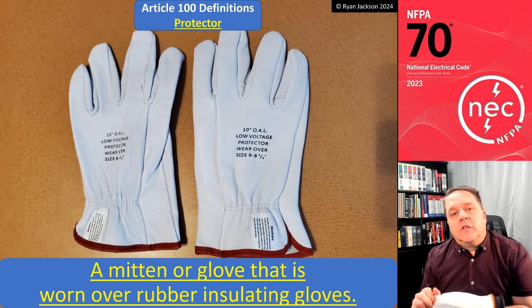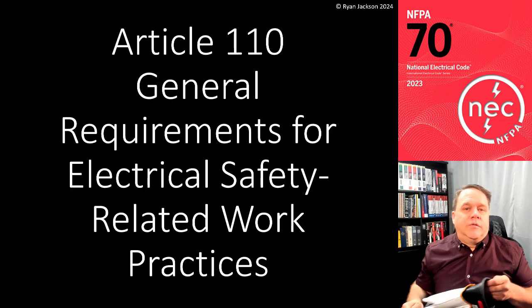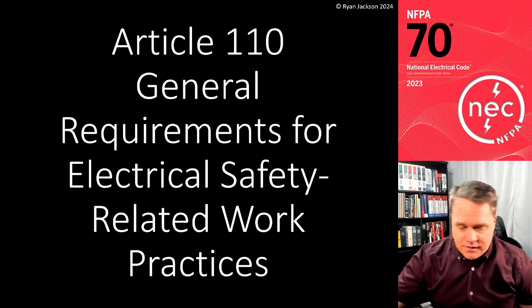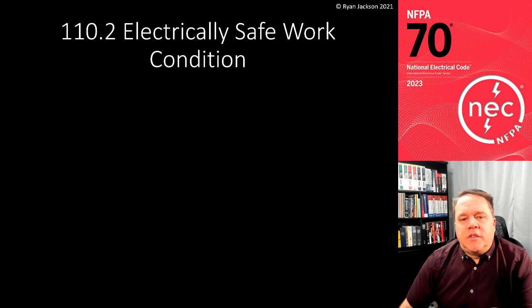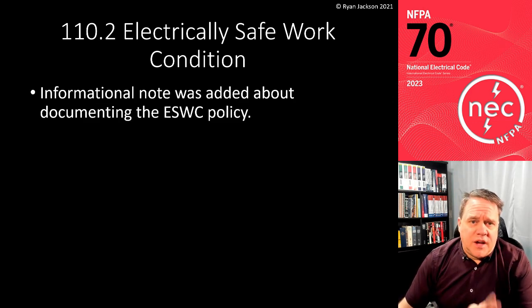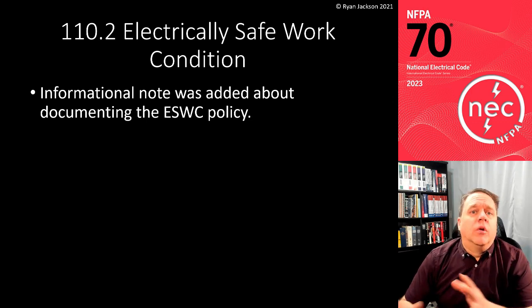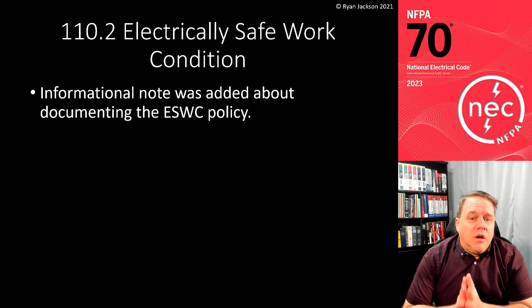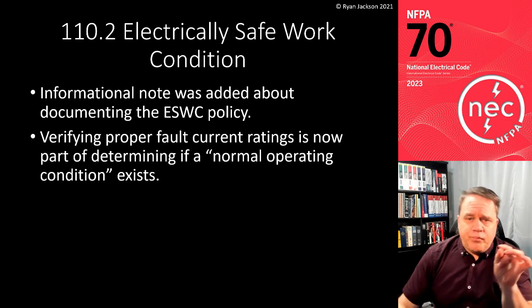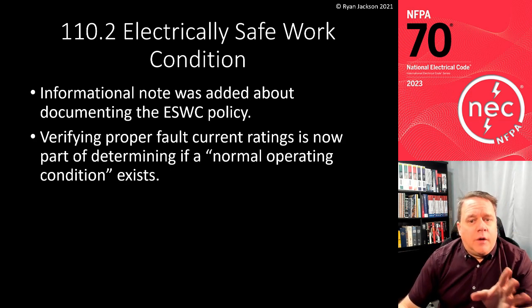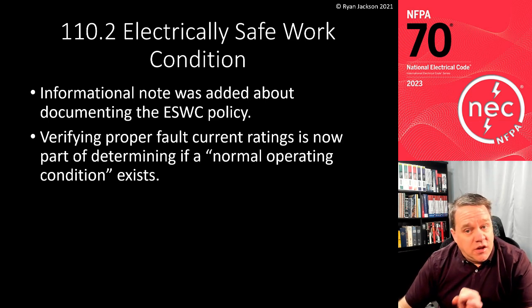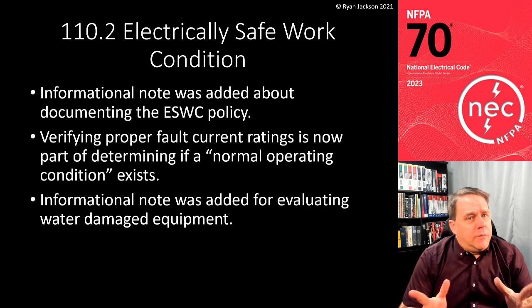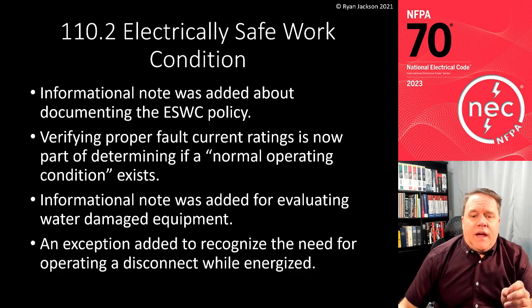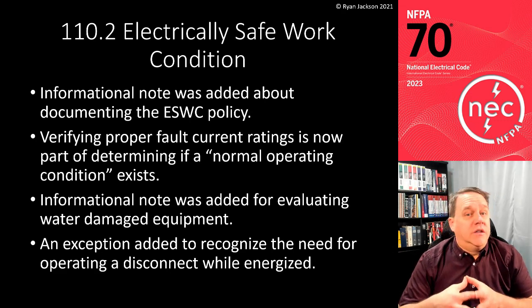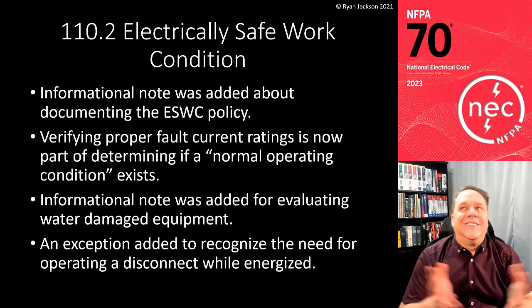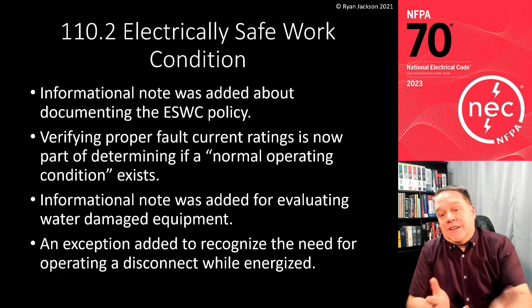All right, let's move into Article 110, which is General Requirements for Electrical Safety-Related Work Practices. Let's start with 110.2, Electrically Safe Work Condition. Super important section in NFPA 70E. 110.2 is one of the most important sections in the entire book. We added an informational note about documenting the electrically safe work policy. Verifying proper fault current ratings is now part of determining whether or not a normal operating condition exists. Super important section there. An informational note was added for evaluating water-damaged equipment, and an exception was added to recognize the need for operating a disconnect while it's energized. That one's almost like an eye-rolling change, but technically it probably does need to be there.